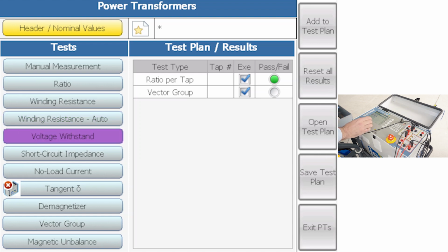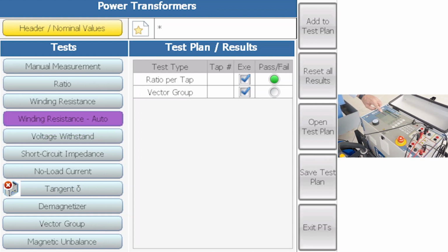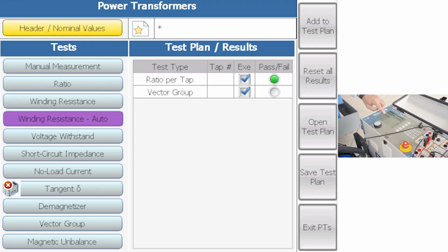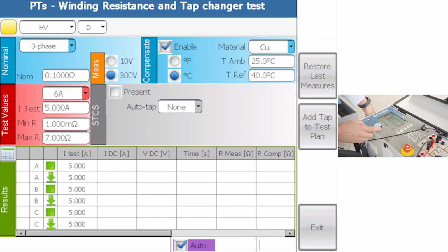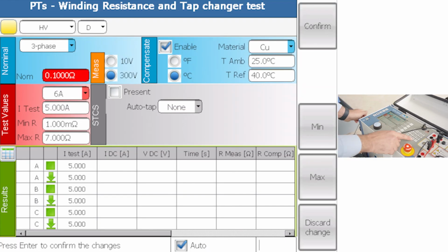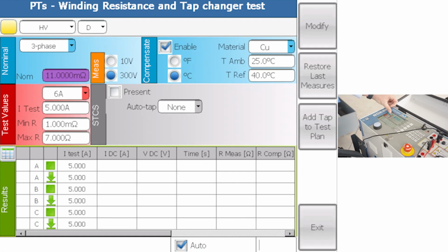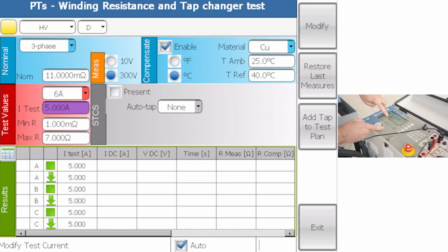Now, I choose winding resistance in an automatic mode. I think, well, we've done some measurement, and the nominal resistance should be around 10 milliohms, so 0.0, let me say 11 maybe. This is not necessary to write, but if you know the value, it's good to write because then you will get an automatic pass or fail. And I will choose 5 amps to generate.